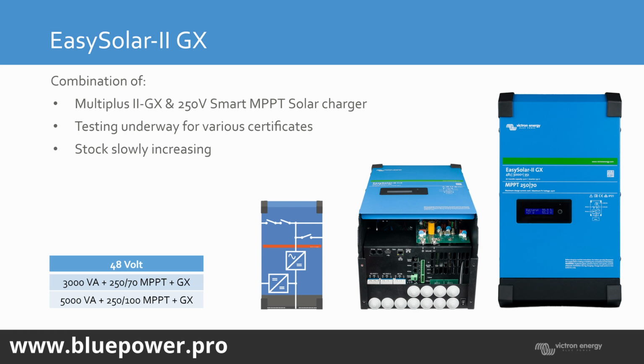So on the inverter charger range, Victron has got the Multiplus starting from 500 VA, so it's a small unit. They can only be set up in 3-phase. They can't be parallel to anything. So those small units from 500 to 1600 VA can only be set up in 3-phase, but they can't be paralleled. But they're nice and compact inverter charger units, also with the transformer built in.